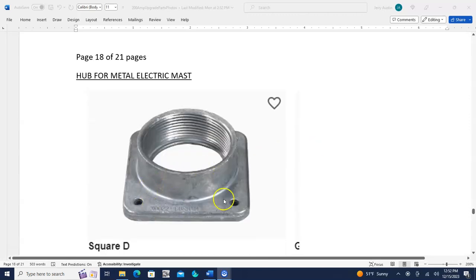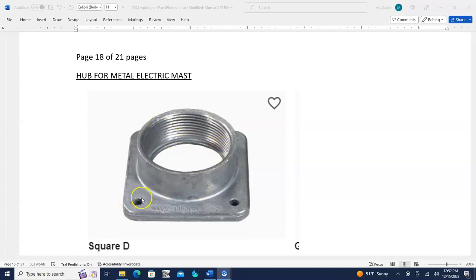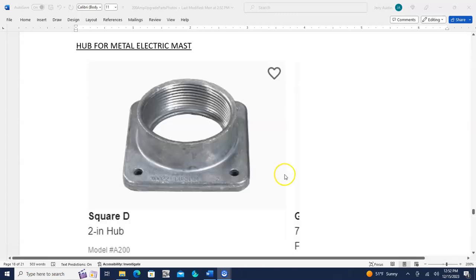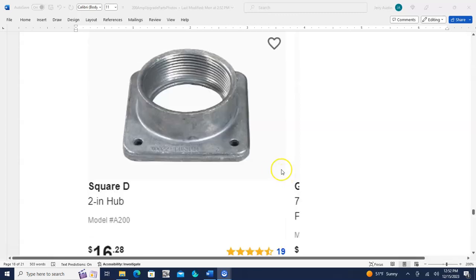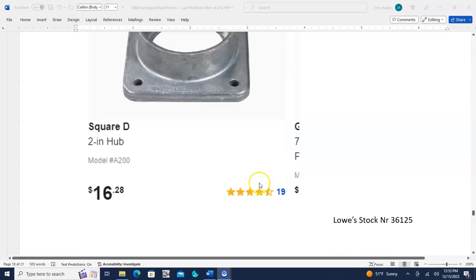There's your hub that sits on top of the meter base, that metallic shaft sits into it. This is clamped or screwed right down on top of the meter base, and it holds that shaft real good and tight. You also have those clamps where you attach the shaft to the side of the house.